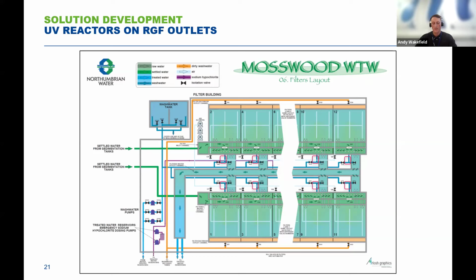And there were a lot of positives for this proposed design at this stage compared to the other options. So it was essentially much lower in overall cost. The potential buildability concerns within the existing assets were much more favourable than having to construct an entirely new treatment stage or procure additional land. The reactors also had lower energy costs associated with them, although we did need to consider power arrangements for the site, which Peter will touch on later. It would minimize impact on the site during project delivery, so we're able to commission and get the asset in use with minimal impact on site output. And essentially, this system could be fully automated and integrated into the operational control and the filter backwashing process.